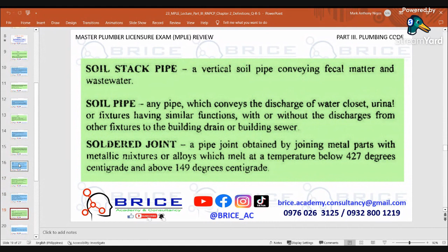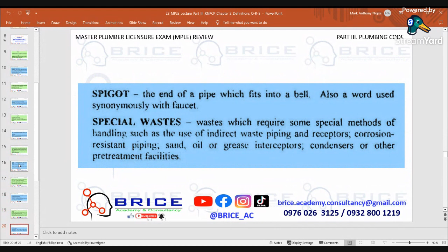Special waste, which requires some special methods of handling, such as the use of indirect waste piping and receptors, corrosion-resistant piping, sand, oil or grease interceptors, condensers, or other pre-treatment facilities. Stack, a vertical main of a system of soil, waste or vent piping extending through one or more stories and extended through the roof.